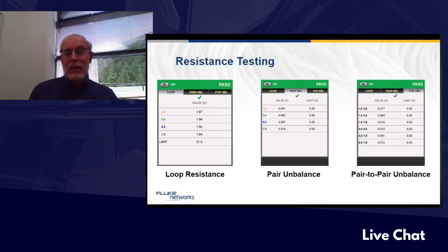Now, what I was talking about with the resistance measurements, certification, and all that—as much as I'd like to tell people to go buy a tester and do this testing on a weekly basis, you don't need to. You really only need to do it once, when you install the cabling. In fact, most customers don't do that themselves; they hire a contractor who comes in, and you just need to make sure they're doing the right kind of testing. Then you're really not going to have anything to worry about.